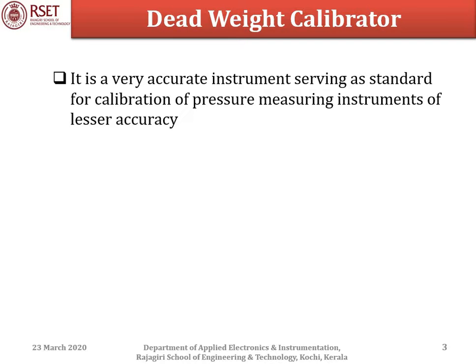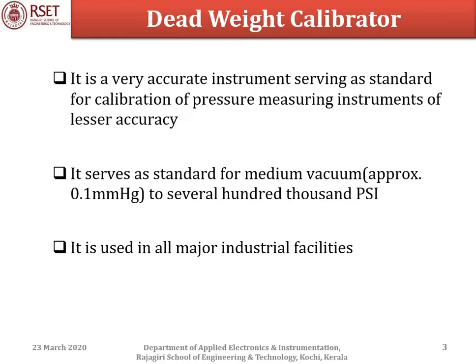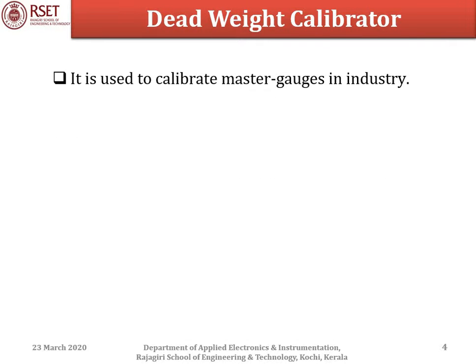A deadweight calibrator is a very accurate instrument serving as a standard for calibration of pressure measuring instruments of lesser accuracy. By standard, we mean an instrument that acts as a reference for readings taken by some other instrument, acting as the true value to compare against. It is used in the range from 0.1 mm of mercury to several hundred thousand psi, in all major industrial facilities, and to calibrate master gauges. Master gauges are gauges which act as reference for calibrating other gauges used more frequently.